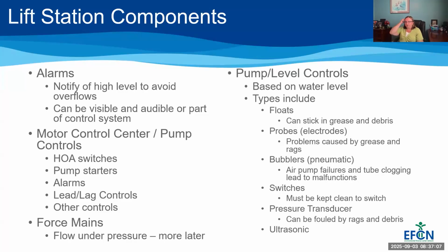And then your pump controls or your level controls. This is what tells your pump when to turn on and turn off. It is based on the water level in the wet well itself. So there are different types of pump controls out there. The most common type, and I think what you guys all have, are floats that float in the water. Whenever the water gets high enough, the float lifts up and it's not hanging on a cord anymore. Now all the pressure's been taken off the cord, and it says, oh, the water's here now. So something can happen. It can turn on or it can turn off when the float hangs again.